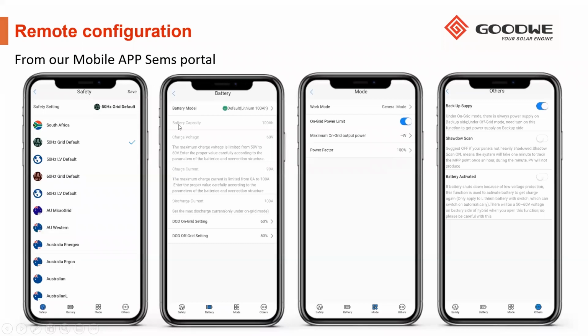To do these settings, there has to be a stable Wi-Fi connection to the inverter, and the newer the firmware on the device, the better the settings work. If the ARM firmware version is below 8, these settings may not work at all.